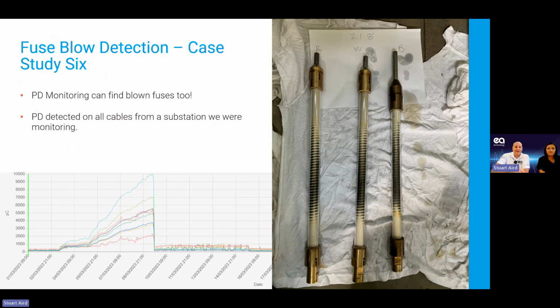And then this is another one. This is actually a bit of a strange one. It causes partial discharge when an actual fuse blows within a VT. So on a high voltage VT, the big ones have these fuses within them, and if the fuse itself blows, you've got a separation. Then you can start to get actual tracking across the fuse, because the path it normally uses right through the middle of the fuse is no longer there. It tries to go around the outside, and you start getting tracking on the outside of that, and that causes really high partial discharge type patterns.